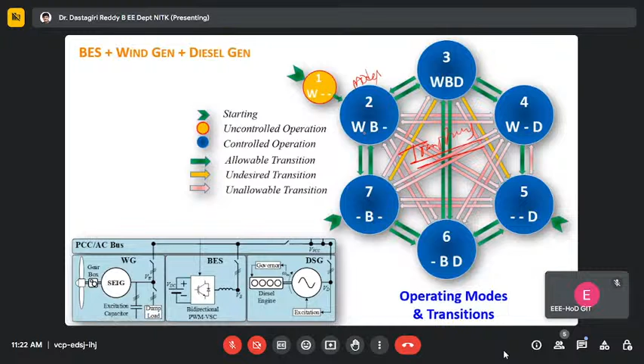Let us see some situations why you need to go from one mode to another. For example, if you take only wind, without a power converter it cannot maintain constant voltage and constant frequency, so it is uncontrolled operation. As wind changes, voltage changes, frequency changes, so you can't maintain constant voltage. In this case battery is not operating, diesel is not operating.